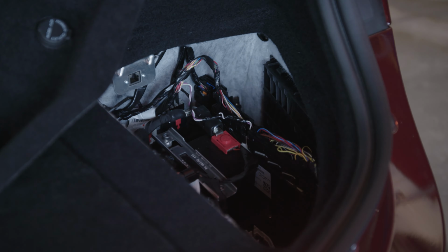That should prevent the fire spread from growing to adjacent objects or combustibles. If option two is selected, then first responders must understand the end objective. The end objective is to apply cooling material to the interior of the battery packs and battery modules to actively cool the lithium-ion battery cells. The most effective agent that can be applied to lithium-ion batteries for cooling is water. No other suppression agents are authorized unless used in a short-term application and only in the absence of water.